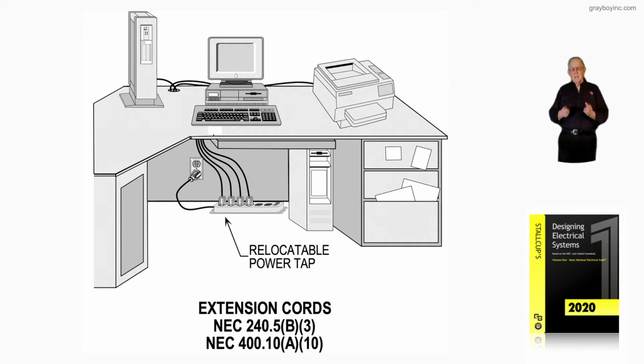And then if you're at a desk location like this, and you use a cable, you relocate a power tap, and you're relocating it. We used to call these temporary power taps, but UL renamed them because you can plug them in or relocate them somewhere else. But notice the one you see there, if you count, you have 1, 2, 3, 4, 5, 6 openings that you could plug something in. Now, that's plugged into a duplex receptacle. If you had 10, that's 20 openings there.